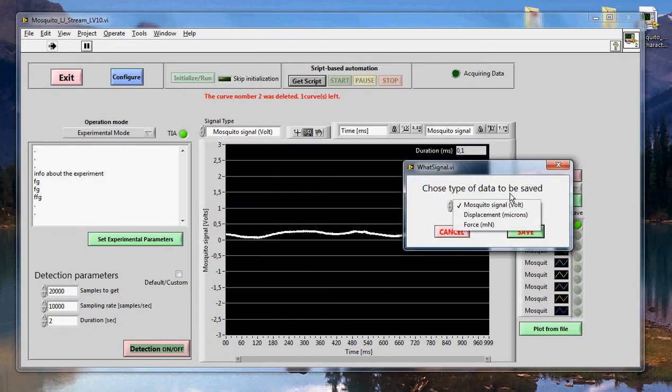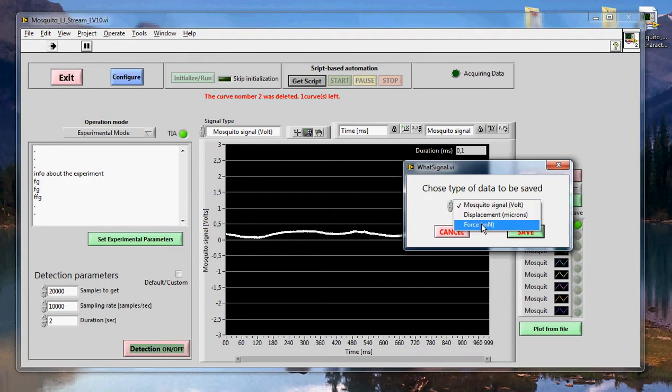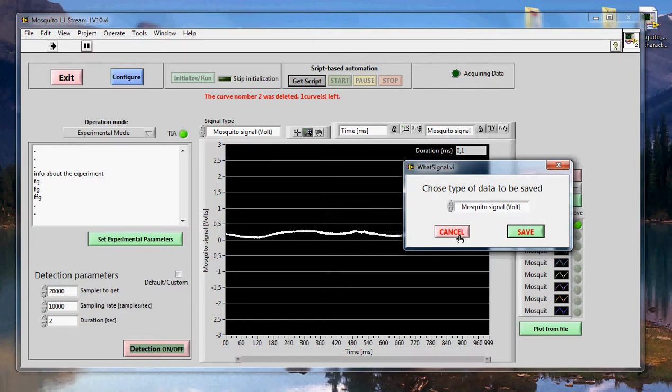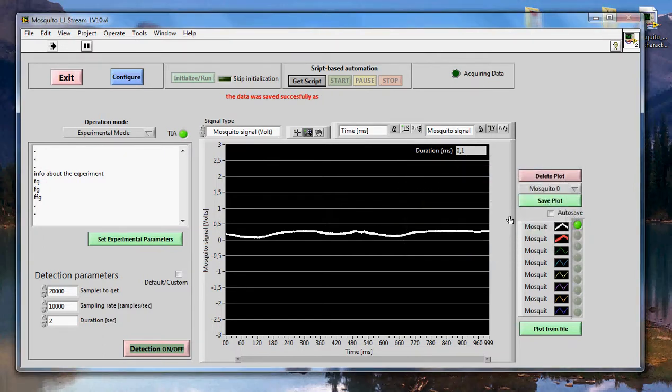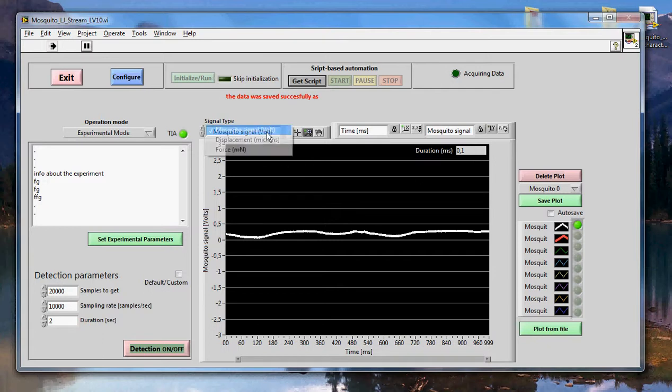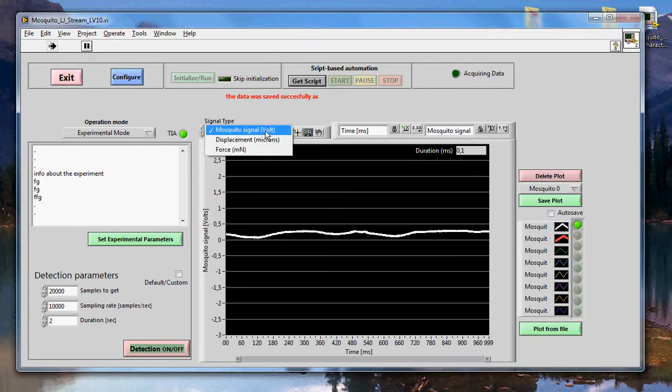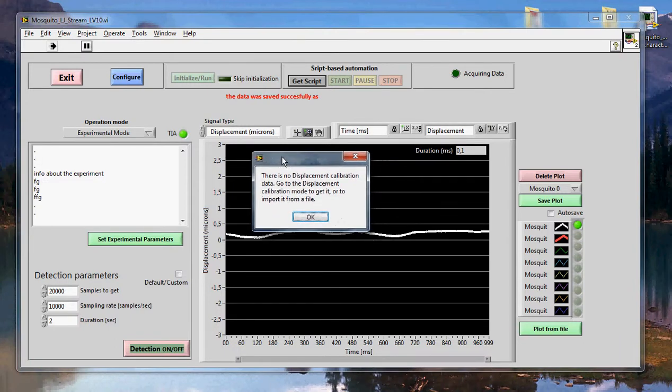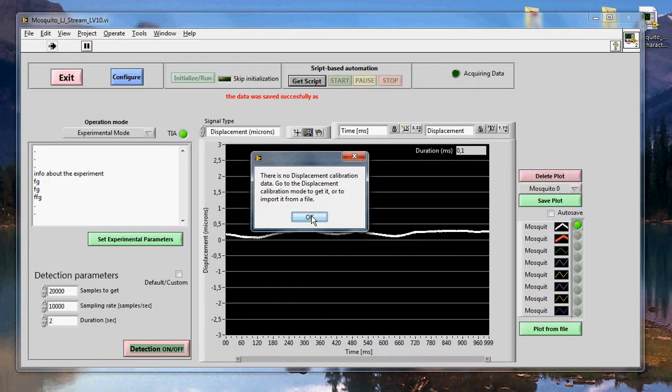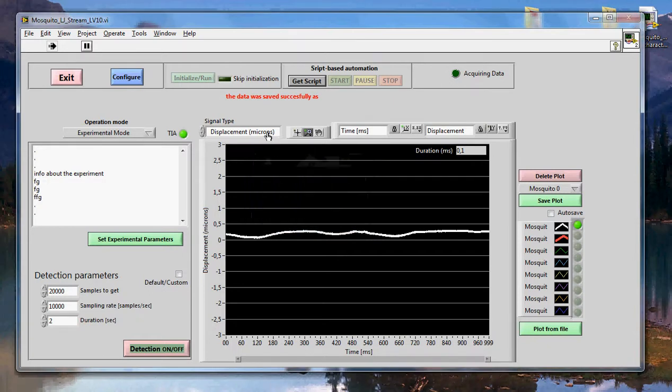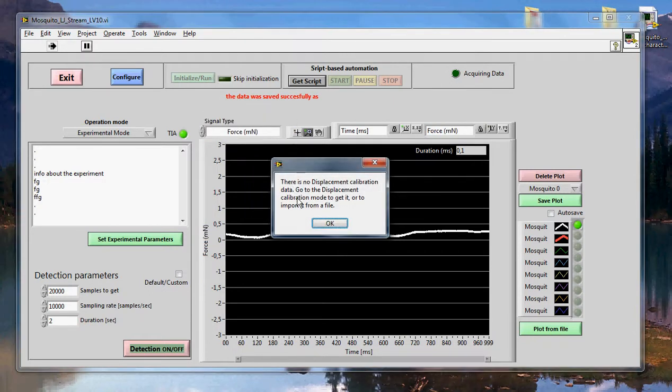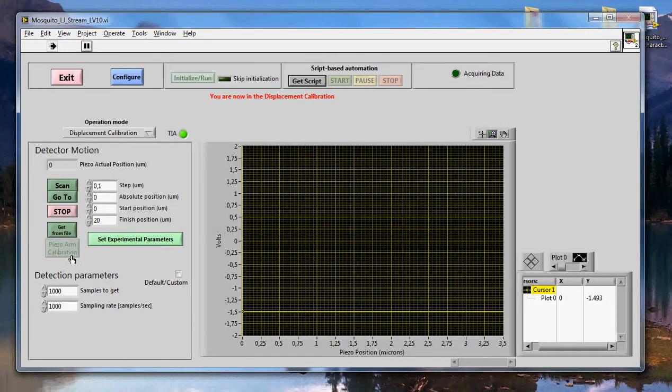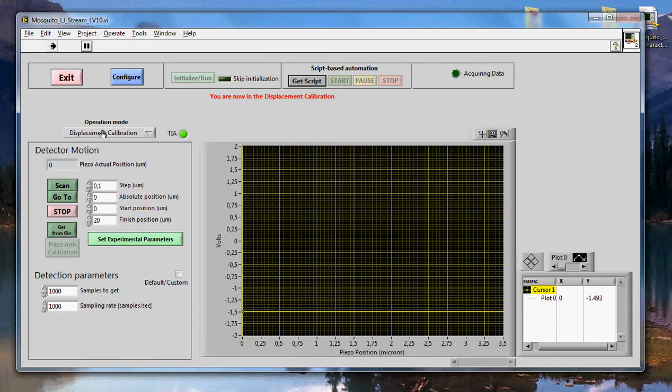Here you can choose to save the raw signal, the displacement or the force. You cannot save displacement and force until you have a displacement calibration curve. So let's save the mosquito signal in volts for now. There we go. The data was saved. Here you can also display displacement or force. But since we don't have a displacement calibration curve, if I put displacement, the system is going to tell me that there is no displacement calibration curve. Basically it doesn't want to do anything because it doesn't have the information to transfer volts into displacement or into force. This is where we could go back to the displacement calibration operation mode and get the displacement calibration curve or get a file from memory.